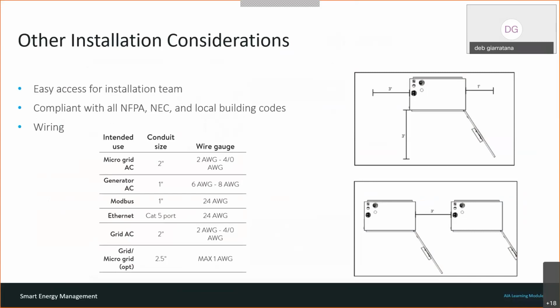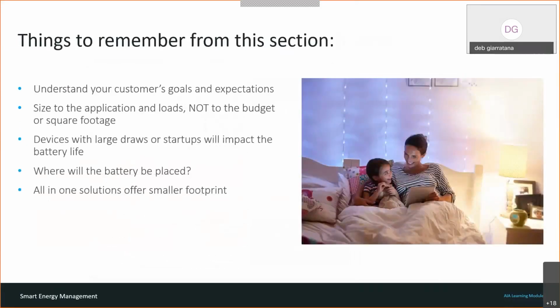Let's go to the next slide. So for things to remember when designing, you really want to make sure you understand: are your clients using this for time of use? Are they backing it up? Are they hoping to be self-consumption based, producing and using the energy that they're producing? We're going to size to the application and the loads, not to their budget and not to the size of their home. Devices with large draws like pool pumps and large AC systems will impact the battery life, and will greatly reduce the length of time that battery can power those devices.